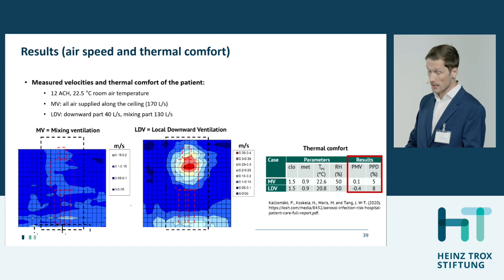However, in the local downward case, also seen in the smoke visualizations, you can see that there's a flow which actually hits the patient. So that's why we have higher velocities with the local downward ventilation case, reaching up to 0.3, 0.35 meters per second. However, although those are relatively high velocities, when we measure the thermal comfort, you can see over there on the right that with mixing ventilation, the PMV value was 0.1, and with the local downward ventilation case, it was minus 0.4. So both quite close to the zero, which is the neutral thermal comfort in this PMV index. So both were quite close to the neutral sensation.